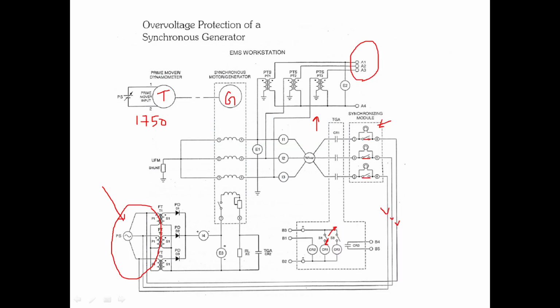We already understood this. When CR2 is energized, the CR2 contact will be closed initially. So when there is no fault, the current flows through this shorted path. You see the current is flowing bypassing the resistor, through the closed contact. This is the normal direction of current flow in the excitation circuit. Now when you disconnect the load, there is over voltage. How do we reduce the over voltage? We have to decrease the excitation current. How? We just open this contact.